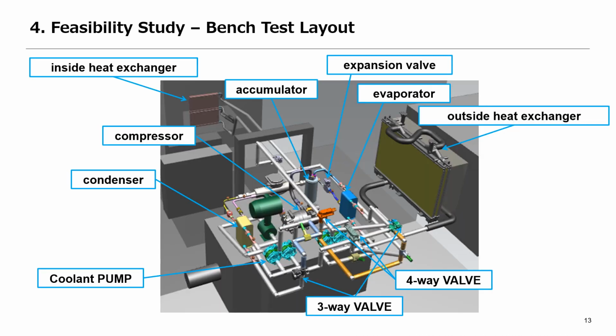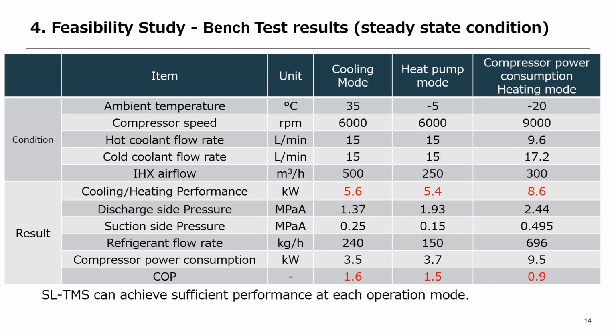This slide illustrates the bench test layout. It features a refrigerant circuit comprised of a compressor, a coolant circuit equipped with a pump, and both inside and outside heat exchangers. This slide presents the bench test results across the three operating modes. In the cooling mode, we achieved a cooling performance of 5.6 kilowatts at an ambient temperature of 35 degrees Celsius. In the heat pump mode, we delivered a heating performance of 5.4 kilowatts with an ambient temperature of -5 degrees Celsius. In the compressor power consumption mode, we demonstrated the highest heating performance of 8.6 kilowatts at an ambient temperature of -20 degrees Celsius. The results underscore SLTMS's capability to deliver satisfactory performance across all operational modes.